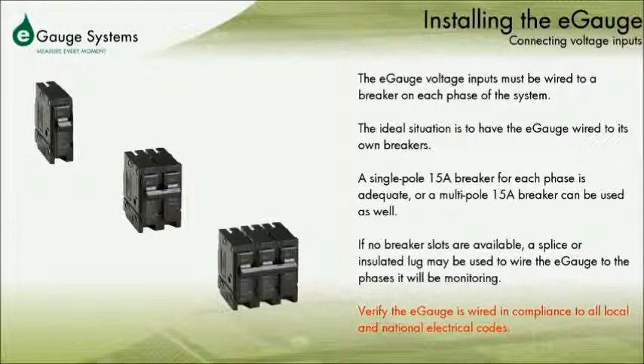The eGauge will need to be wired to a breaker on each of the phases of the electrical system. The ideal situation is for the eGauge to have its own breakers. A single pole 15 amp breaker for each phase is adequate, or a multi-pole 15 amp breaker can be used as well. In cases where there are no available breaker slots for each phase, a splice or insulated lug can be used to wire the eGauge to the phases it will be monitoring. Please make sure the eGauge is wired according to local and national codes.